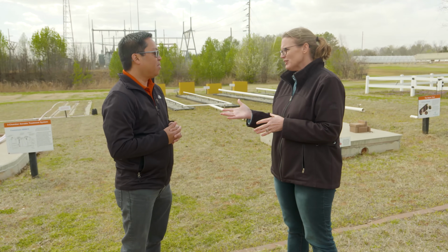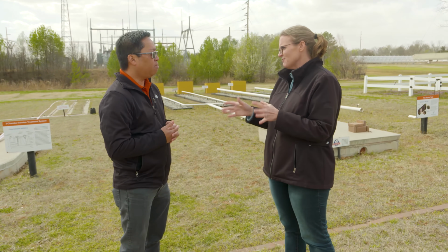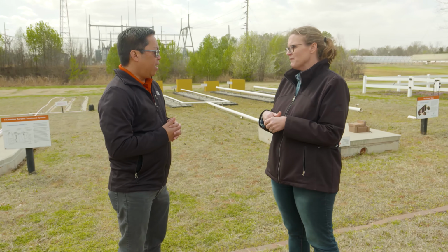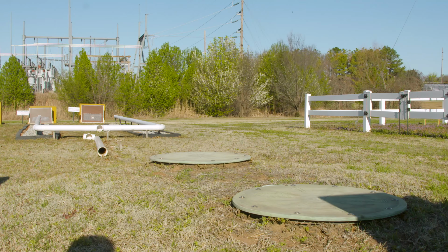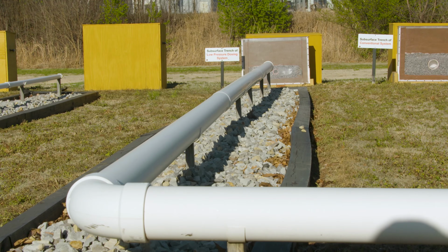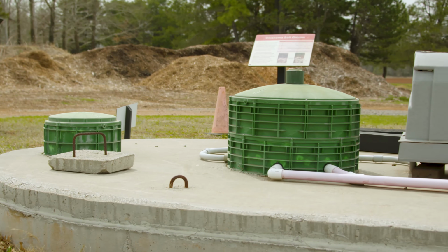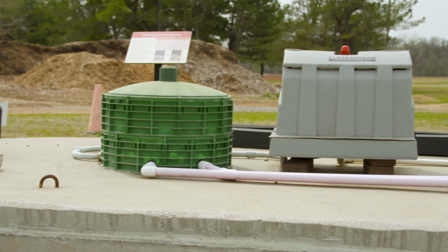Okay, you mentioned pre-treating. Is that septic tank different than your traditional one? It is. In the conventional system, the septic tank is just for temporary storage. You separate the solids from the scum or the grease, and then the effluent is treated in the field. But for the aerobic treatment systems, you have a big tank with different chambers in it.